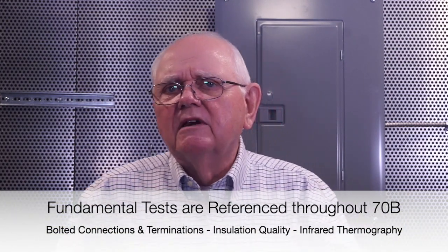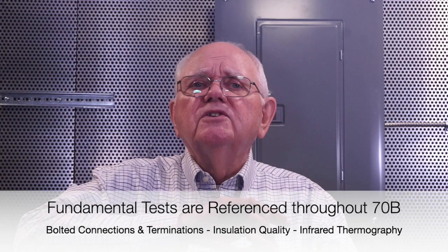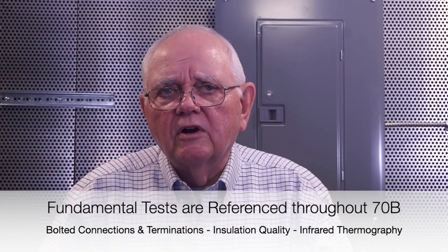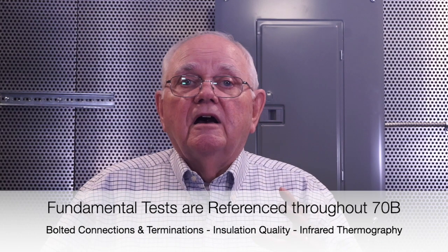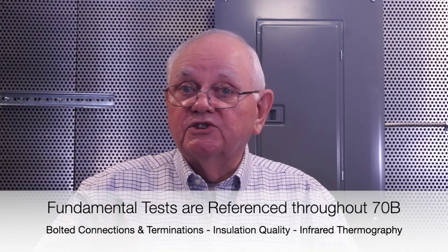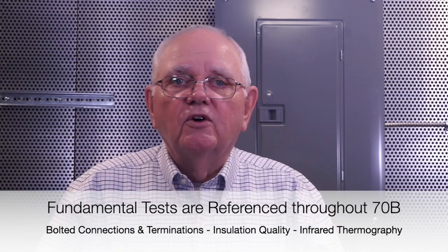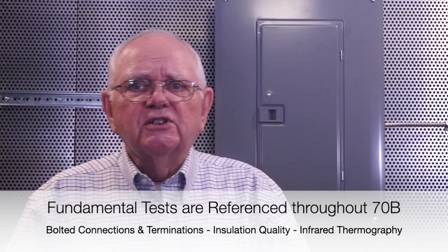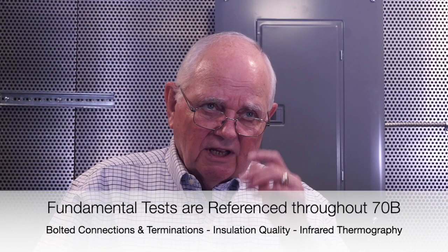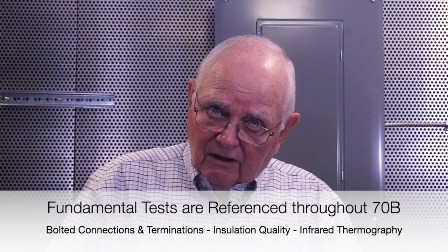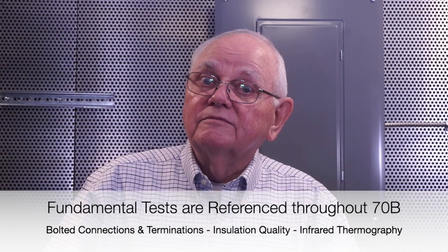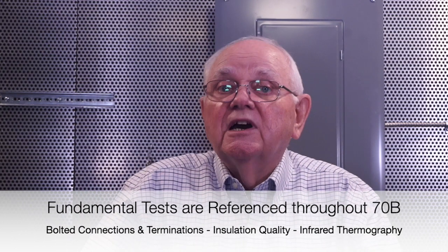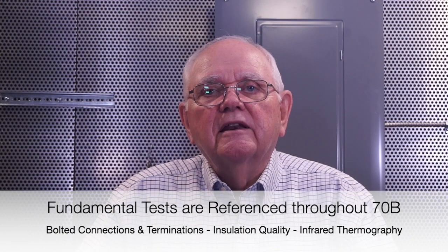As far as the fundamental tests then that are identified in NFPA 70B, it takes a look at a few things. And this applies to all the types of equipment that we're going to go out there and work on. We have to look at things like bolted bus connections, conductor terminations inside of control panels and so forth, conductor connections, and especially things like on a disconnecting means, like a 3-phase disconnect, safety switch or whatever. We don't want those overheating. So one of the best things we can do, 70B tells us, is an infrared survey on that equipment. And so we need to follow and go through our procedures for infrared surveys.